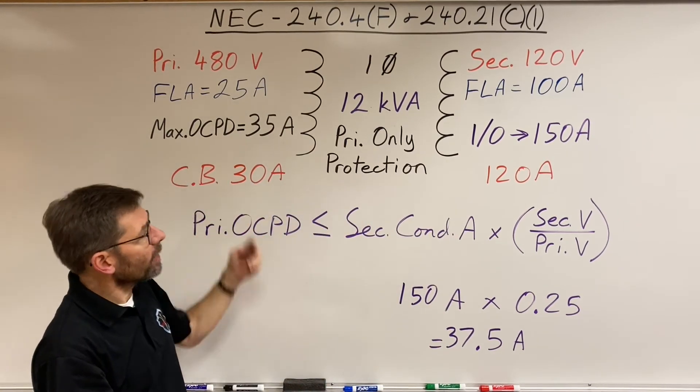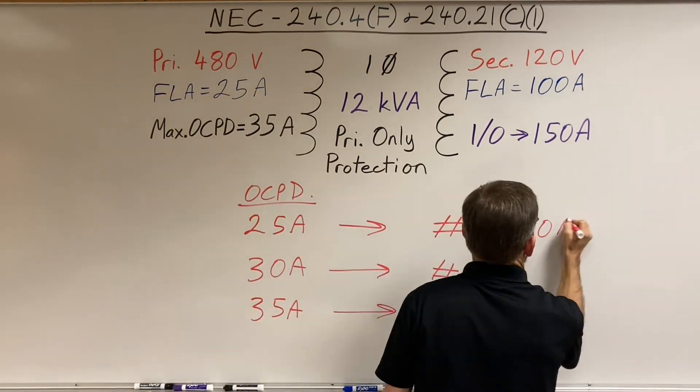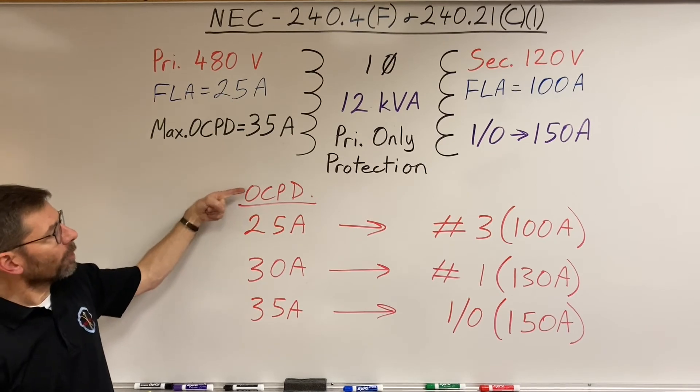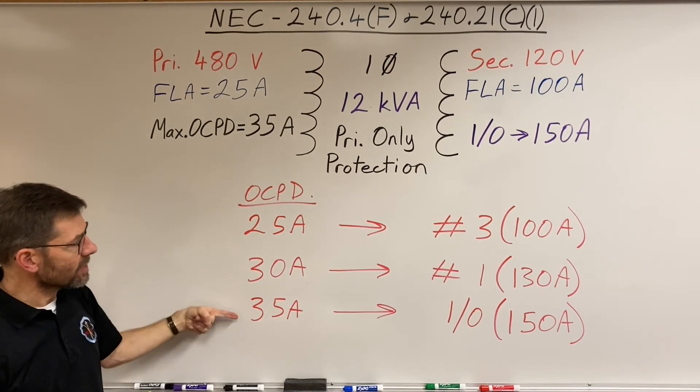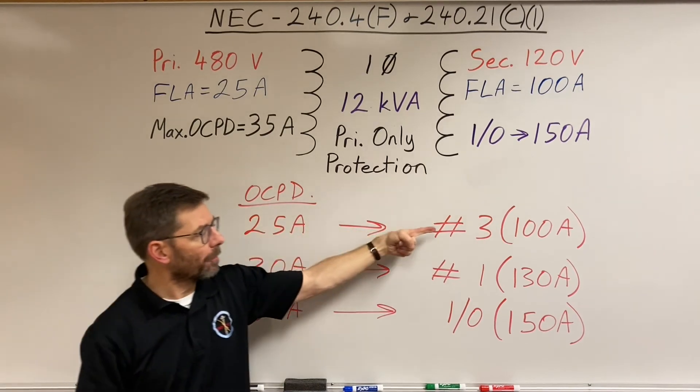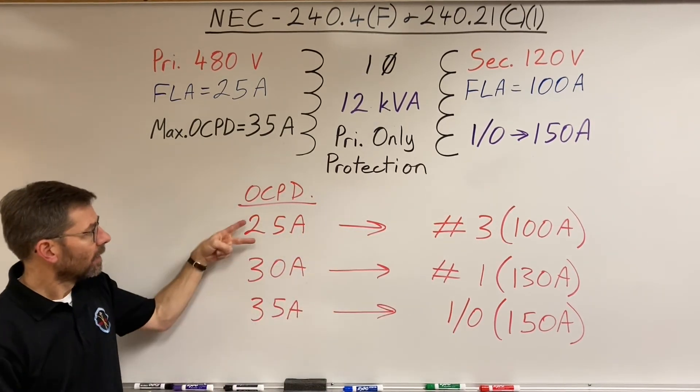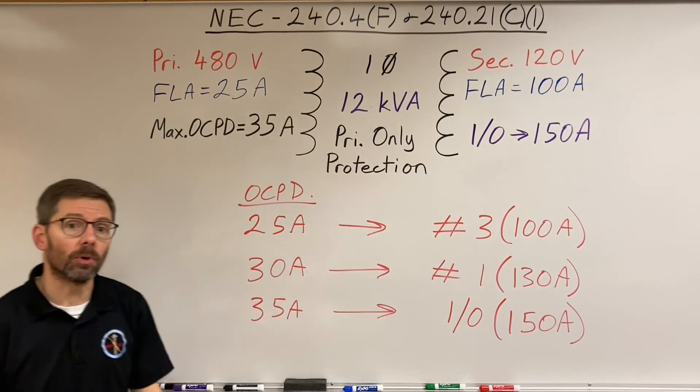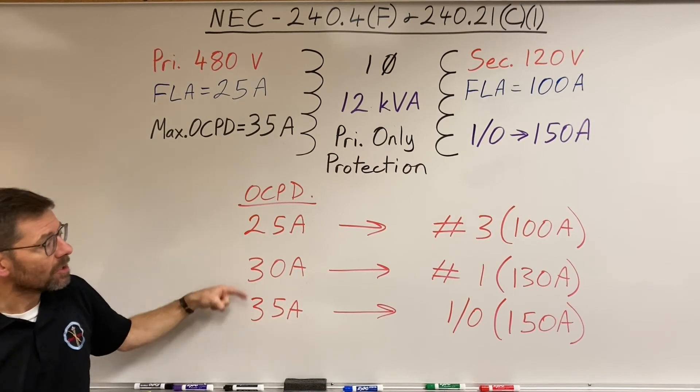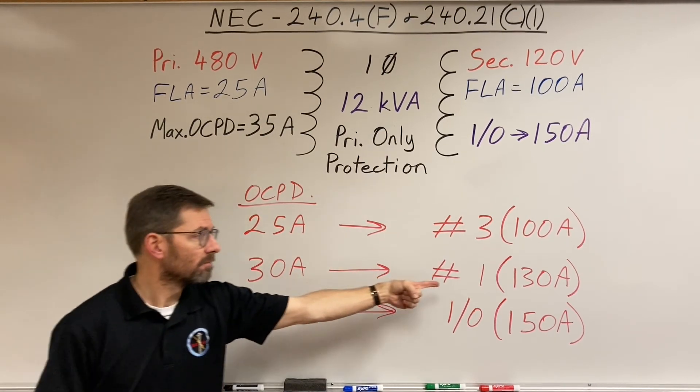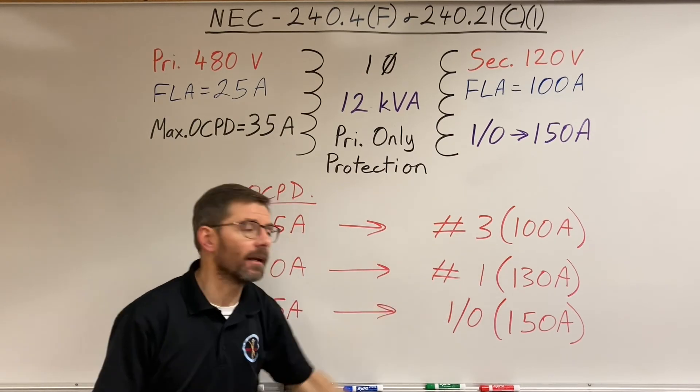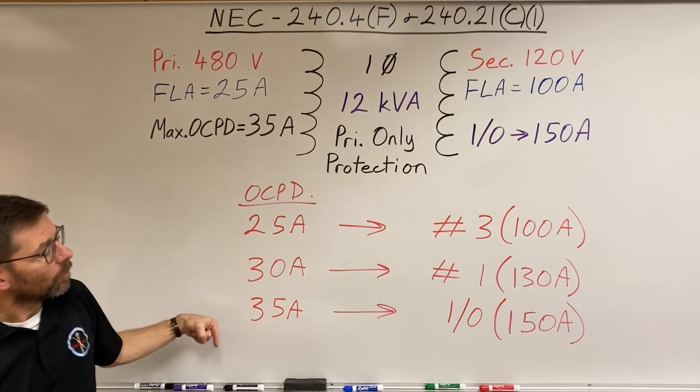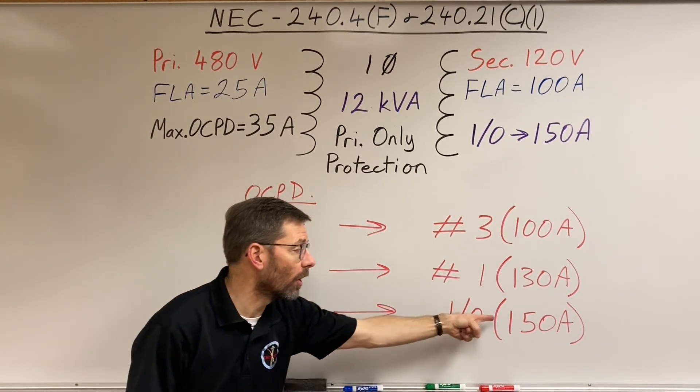I could essentially use a 30 amp breaker and do it this way. If my overcurrent protective device were these various sizes, that would be how big the secondary conductor would need to be. 25 amps would result in 100 amps on the secondary, 30 amps would require 120 amps, and a 35 amp would allow 140 amps. So I've got to use a one-aught for 150 amps.